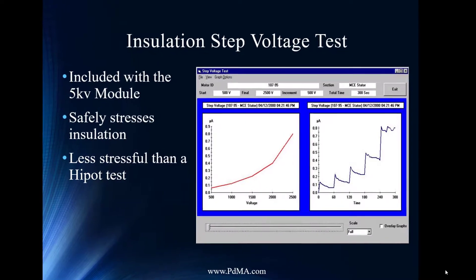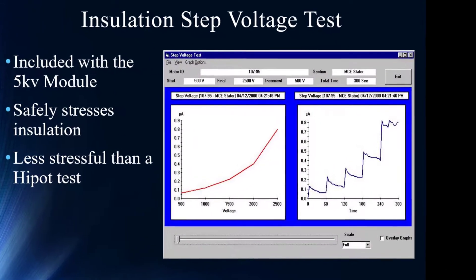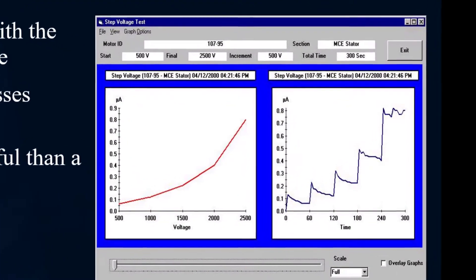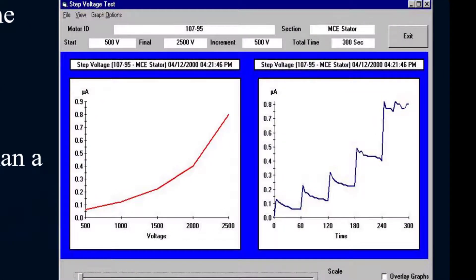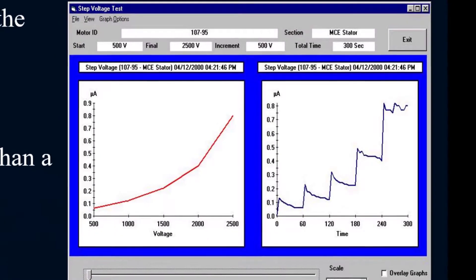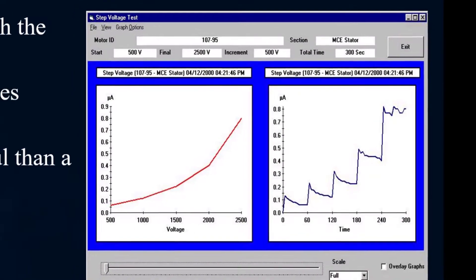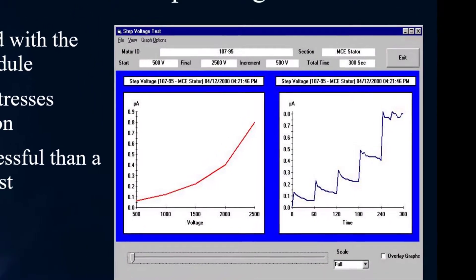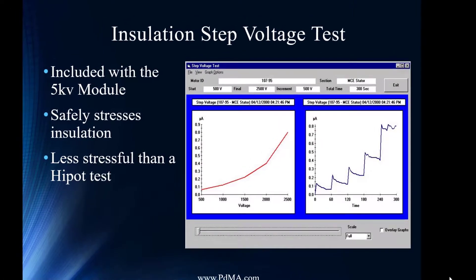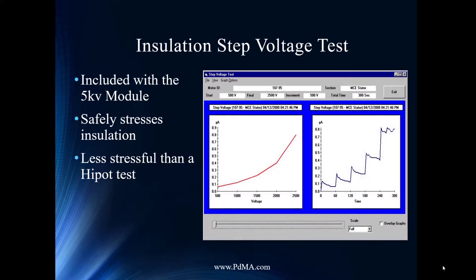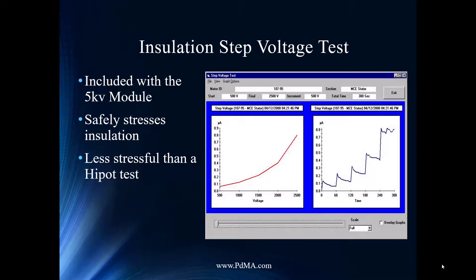Another test available on the MCE Max is the Step Voltage test. Similar to the PI test but rather than a steady voltage held for 600 seconds, the voltage is stepped up every minute while measuring the insulation response in microamps of current rather than resistance. It's typically used as an overvoltage test, but we also use it as a baseline for future comparison. For motors under 2,300 volts, you can safely drive the voltage slightly above line voltage to detect trends. Each voltage step should produce a linear increase in current per Ohm's Law — a non-linear response indicates a problem requiring investigation.